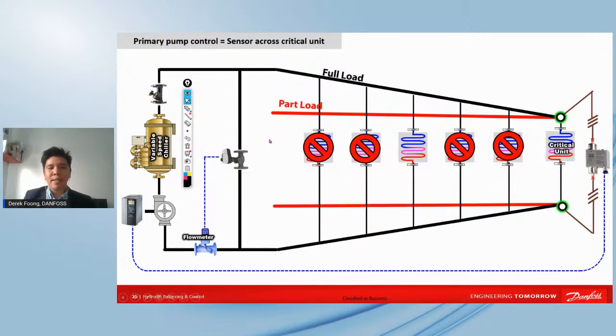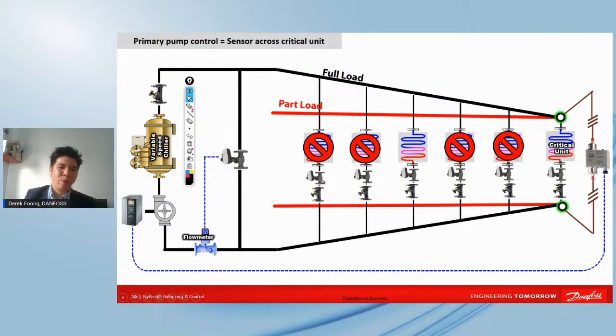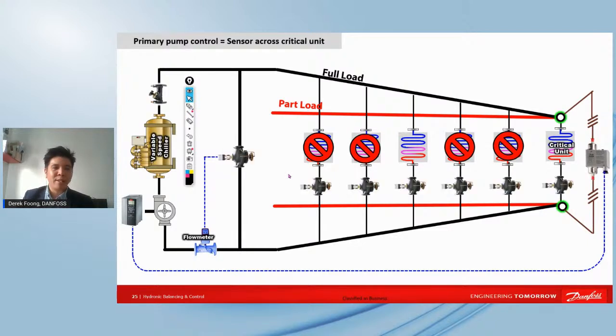Okay, so now another question is, what are the best combinations when you want to achieve the best pumping efficiency? Conventional control valves plus manual balancing valves are considered outdated, and Malaysia is actually taking the lead in Southeast Asia. We can see most of the designs now don't call for this kind of components. They actually integrate pressure independent technology, and I'm very happy to see that. Over the past decade, the adoption of this technology has become more or less matured. 80 to 90% of the tenders actually are open.